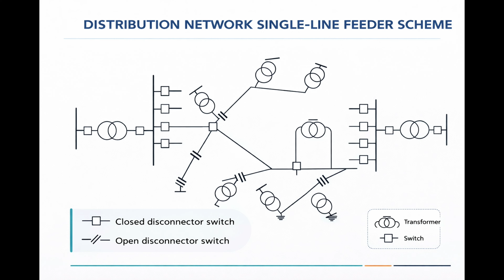Short circuit currents are also higher. This affects protection settings and equipment ratings. The medium voltage feeder is not only a line, it's a structured system with switching points, branching logic, and protection coordination. Your design must ensure clear radial operation under normal conditions. It defines sectionizing points, fast fault isolation, and safe maintenance capabilities. When properly designed, a branched medium voltage feeder provides reliability, flexibility, and economic efficiency.